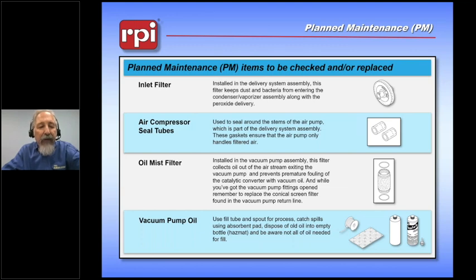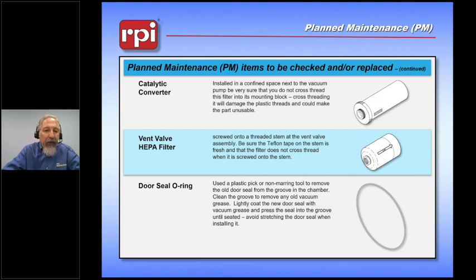The oil that is generated as part of this planned maintenance should be considered hazardous waste, as it will have some hydrogen peroxide mixed in with it. So we want to be sure we handle it correctly, and we have an empty bottle included within the kit, so you have a place to put it. There's a catalytic converter included in these kits. Make sure when you install this that you are careful about these threads. They are just molded. They can cross thread occasionally. Take your time. You should be okay getting it in. It's not that complicated, but it is a very fine thread.